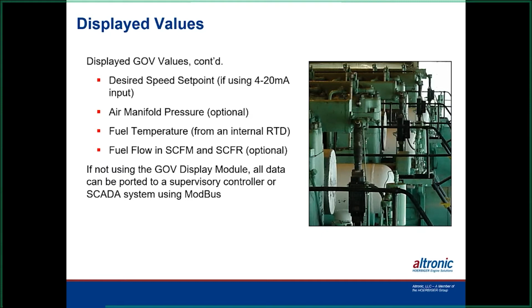Now it has a 4 to 20 output that you can bring into another device to read the RPM on it. You just have to do the scaling on it. And it also has a air manifold pressure place to read that also, and that's an optional thing that can be programmed into it. I don't know if a lot of people are using that, but because they usually pick off that pressure off another transducer inside the panel somewhere.